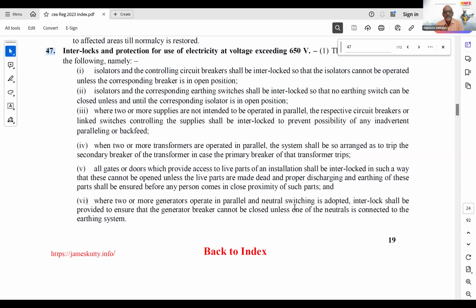See, the thing is, the specific provision, you can see interlock, where you can go through it: where two or more generators operate in parallel and a neutral switching is adopted, interlock shall be provided. So, where it is necessary. The regulation does not say that you must go for the neutral switching. Previously, people were still practicing this neutral switching.